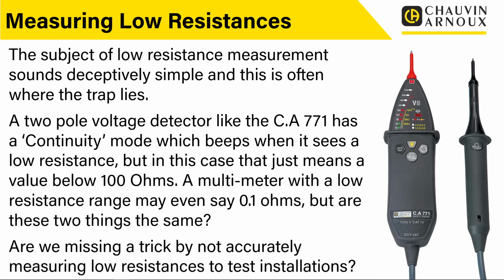And similarly with a multimeter, when we've got a multimeter with a low resistance range, that may even say 0.1 ohms. But are these two things the same? Are we actually getting, when we get a beep on a continuity tester, when we get 0.1 ohms on a multimeter, are these things actually low resistance, and what's the accuracy there? So we will discuss this throughout the rest of the presentation, but it's something just to be aware of, that when we're looking at these things, we need to understand what we're measuring, what we're trying to achieve, and the differences between them. And I think, as we put at the bottom there, are we missing a trick by not accurately measuring low resistances to test installations?